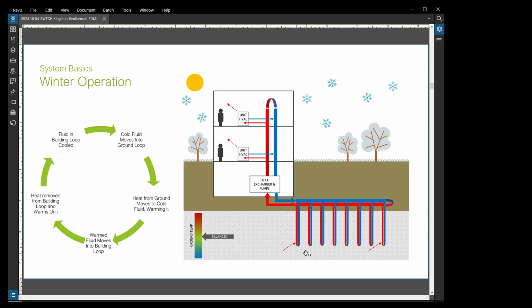So over the span of the heating season, what that does is you've essentially extracted heat from the ground. So if I go back up a slide, your ground temperature, say it was 10 degrees at that depth, at the end of the heating season you would have lowered the ground temperature because you've taken the heat out of the ground and pushed it into the units. And if you were only ever doing that, you would run into a problem, because all of the equipment used to make this work needs the temperature of the fluid in the loop to be within a certain range. If you're constantly reducing the temperature of the ground, the temperature in that fluid will over time eventually fall out of that range, and then you'll have a problem.